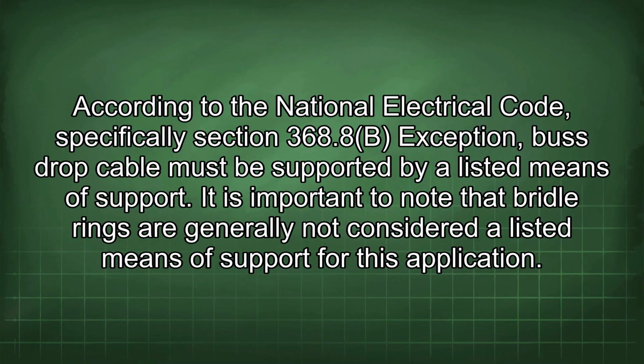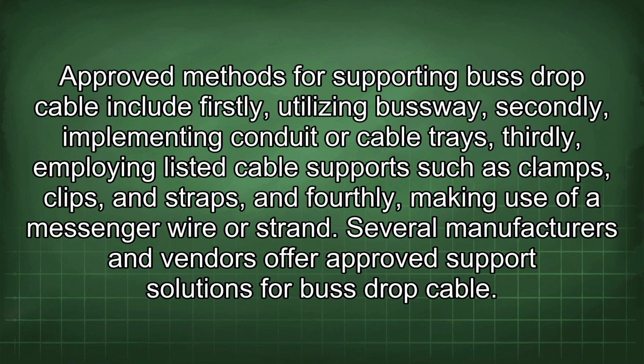According to the National Electrical Code, specifically Section 368.8(B) exception, bus drop cable must be supported by a listed means of support. It is important to note that bridle rings are generally not considered a listed means of support for this application. Approved methods for supporting bus drop cable include, firstly, utilizing busway; secondly, implementing conduit or cable trays; thirdly, employing listed cable supports such as clamps, clips, and straps; and fourthly, making use of a messenger wire or strand.